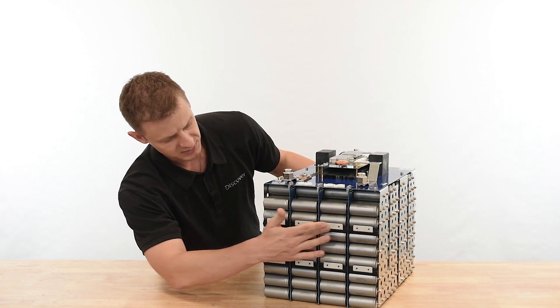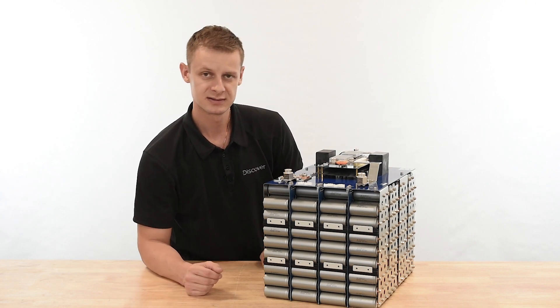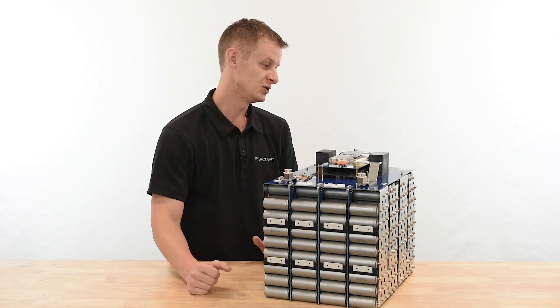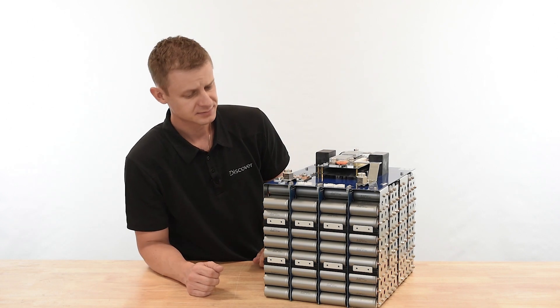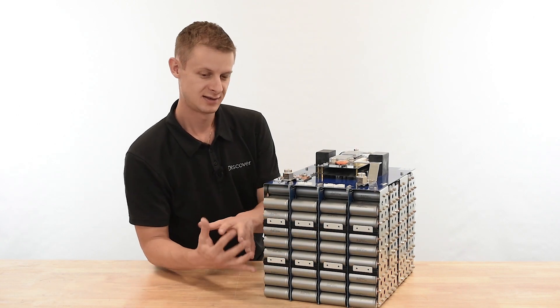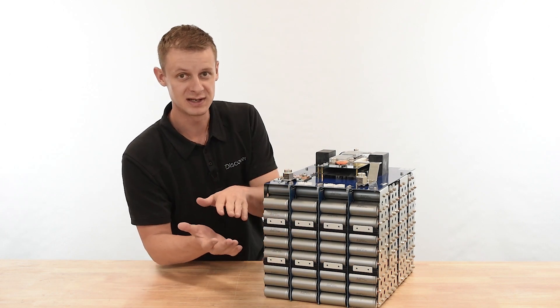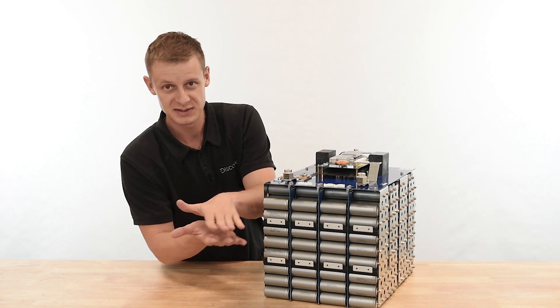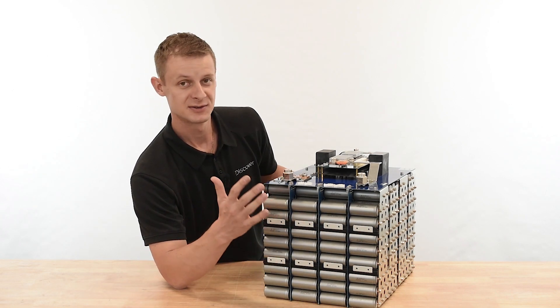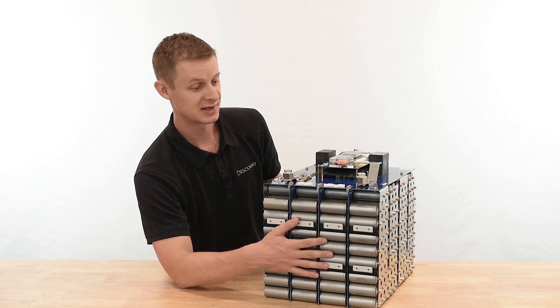You'll also notice some mechanical structures throughout the battery. These came from a lot of learnings in certifications: UN 38.3, UL1973, and UL2271. In order to tie this cell block to the case and couple a tight mass — as opposed to the cell block just floating inside the case, where you'd get two masses moving at different frequencies — we've got this structure here to hold it all together so we don't shake apart during certification shake-and-bake testing.